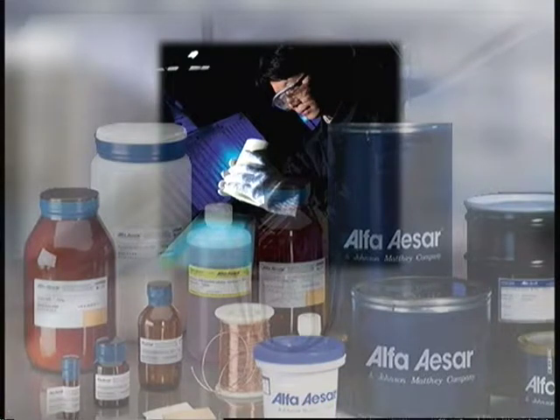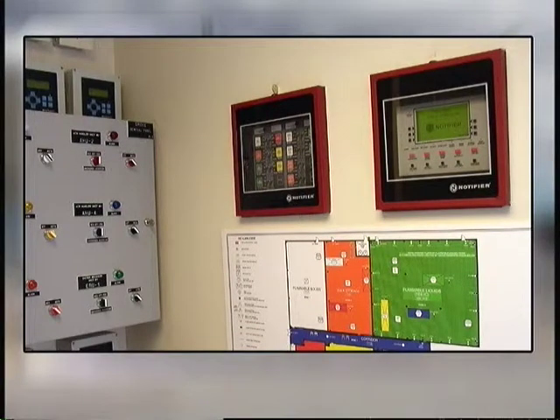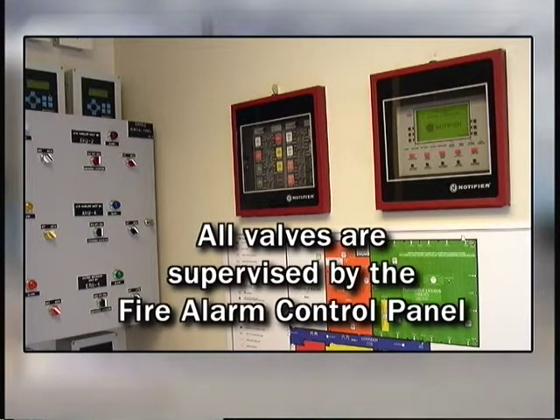Experiences at the Alfa Aesar Bond Street facility have resulted in the requirement to be able to control or shut off the fire protection water supply to certain portions of the facility. Accordingly, in addition to the main sprinkler shutoff valve, portions of the fire protection system are arranged to isolate certain areas. All valves are supervised by the fire alarm control panel and are normally open.